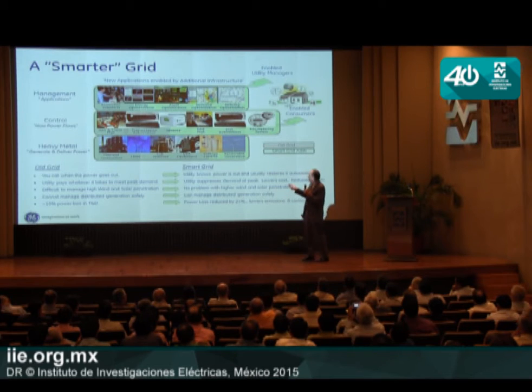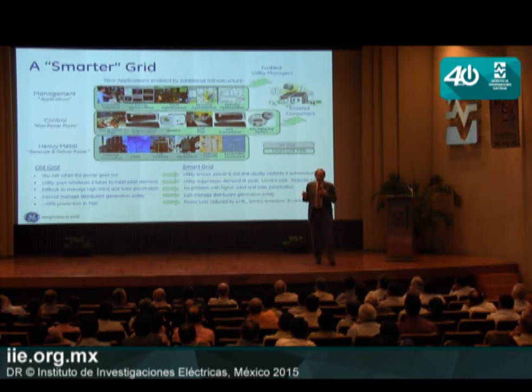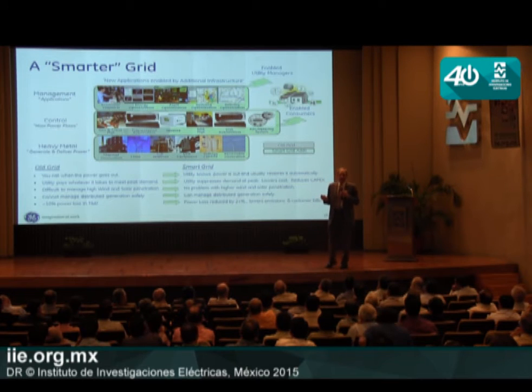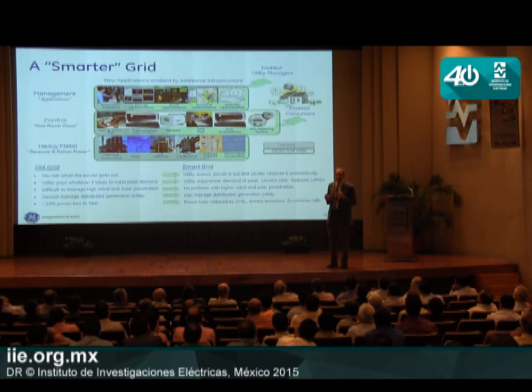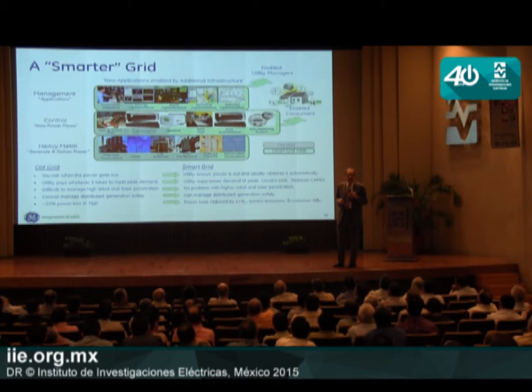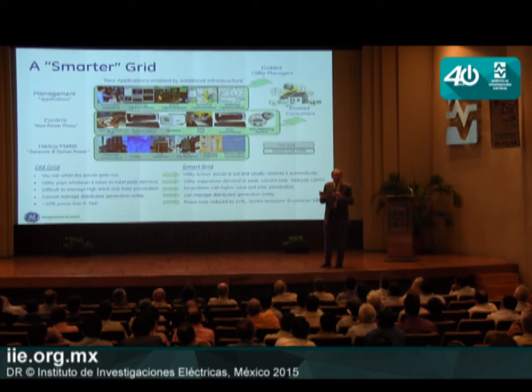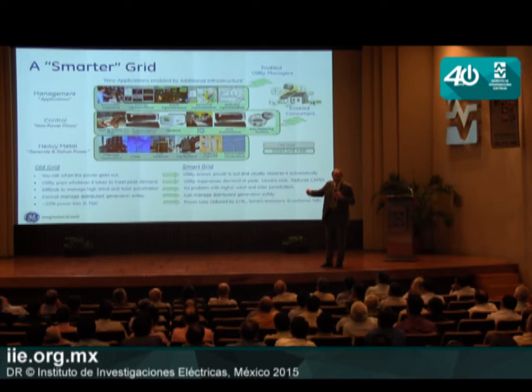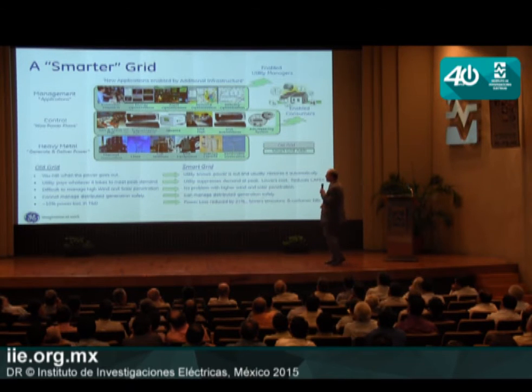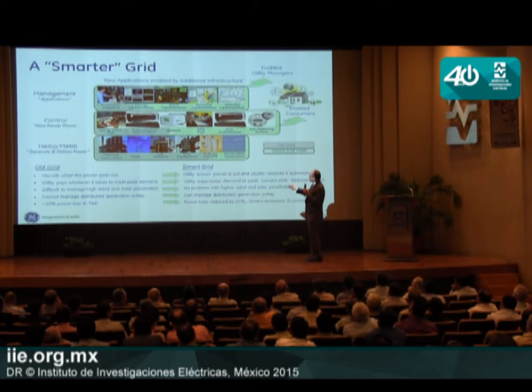For a small amount of money we can invest in microprocessor-based devices like this. We can take the oil from the main tank of the transformer, send it through this device, and it can detect up to nine different gases dissolved in the oil. The presence of any one of those gases is a failure mode occurring in the transformer, so we can know the health of that asset on a continuous basis. Instead of taking a chance and not monitoring a two or three million dollar asset, for a small investment we can add this and know the health continuously, called transformer monitoring and diagnostics. In fact, that's the second strongest business case today of any smart grid solution.